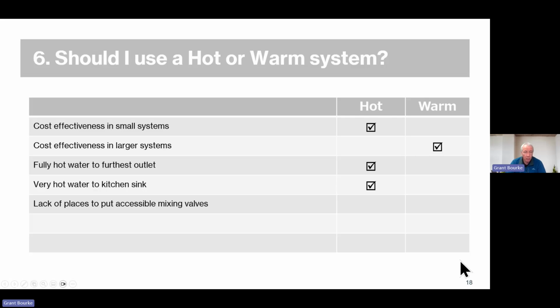Lack of places to put accessible mixing valves. We've seen buildings, high-end homes, where the customer's specified standard of finish was such that they weren't going to accept any hatches anywhere, so the warm water system was the best option for those homes. Cross connection between hot and cold, we've seen it in warm water systems at best. So again, that's why we use them in large buildings, because we might have 200 potential cross connection points. So the warm water system is going to give us much less grief for that.